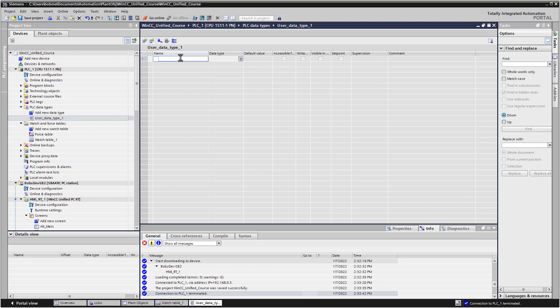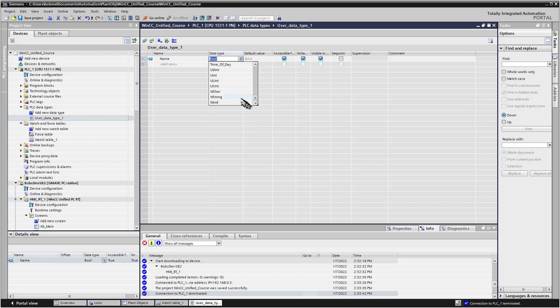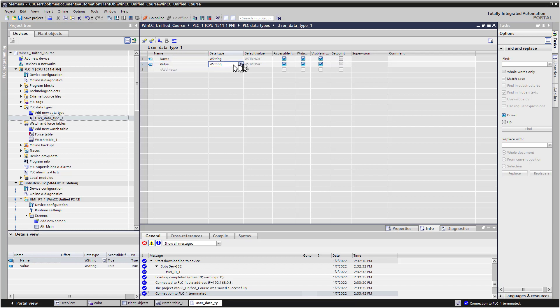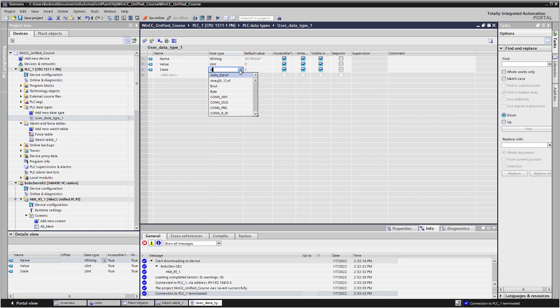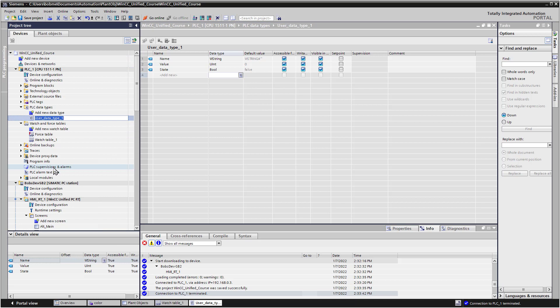For the first thing, I'll do name, and I will give that a data type of a wide string, and value, which is going to be our process value, and data type, I'm just going to do an unsigned integer, and then we'll do state, which will be a Boolean, and then we will go over and just rename this to Equipment UDT.